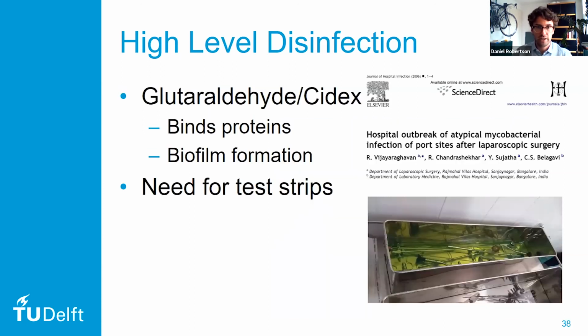And the other one is glutaraldehyde or Cidex. One of the problems with glutaraldehyde is that it binds the proteins onto the surface of the instruments. So all of the instruments have to be absolutely clean before using glutaraldehyde. And one other problem is that glutaraldehyde sometimes leads to bacterial resistance. And that, together with some waste that falls off the instruments, can lead to biofilm formation on the bottom or the side of these Cidex tanks. And this has actually led to several hospital outbreaks, and these outbreaks were related back to the bottom of the Cidex trays. And as I mentioned before, if you do use Cidex, you really have to test it with test strips to see if it's still effective.